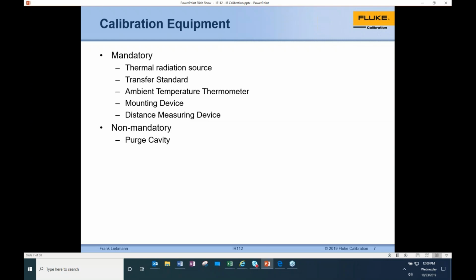So again, with your transfer standard, you've got to have some sort of calibrated standards, maybe a control probe, or it could be another calibrated IR gun that's at a higher level. In-house, when we do our radiometric calibrations, we use these guns that are called KT-19s. They're very high end, and then we calibrate those. And again, we'll dig into that a little bit. But again, that's the transfer standard from us going from the radiometric of the gun to the radiometric calibration of our black body.